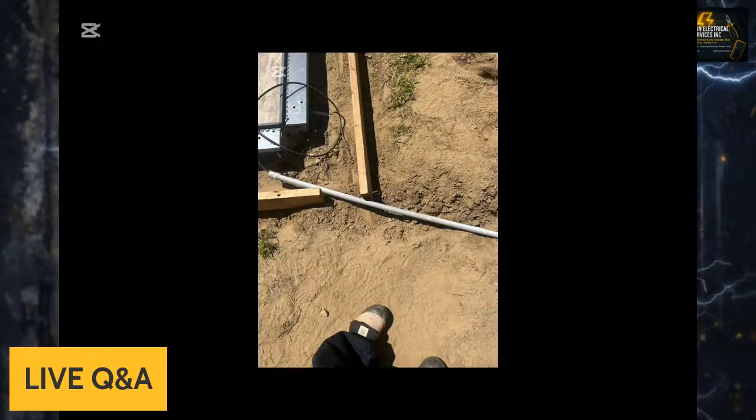When it comes to your sub-panel wiring, a sub-panel with bonded neutrals is wrong. Equipment relying on a ground rod is a no-no. Floating metal parts are also a no-no. So again, in this video, I will break it all down for you: grounding and bonding, the key parts of it, metal parts being grounded and bonded, the whole nine yards, and the importance of following the OESC 2024.